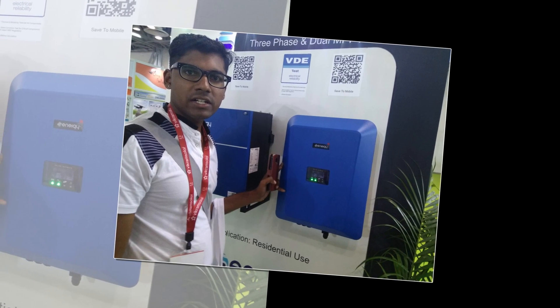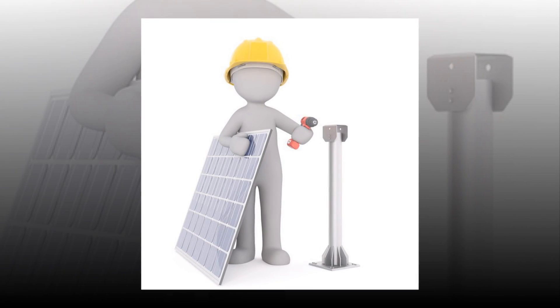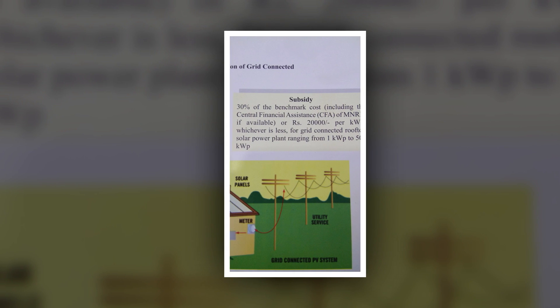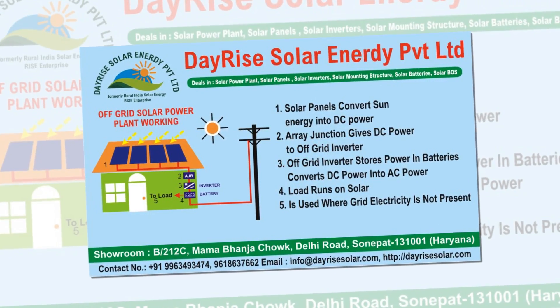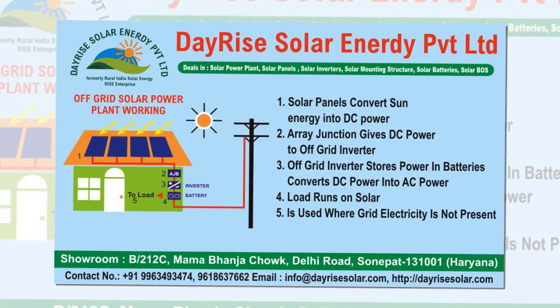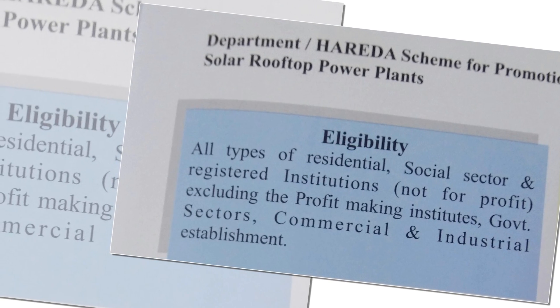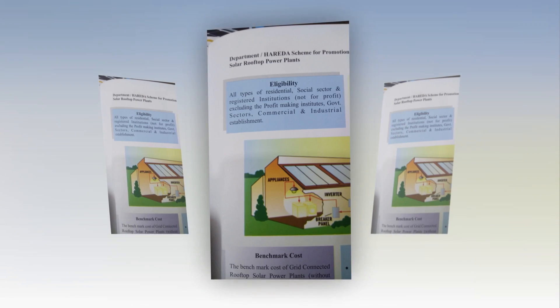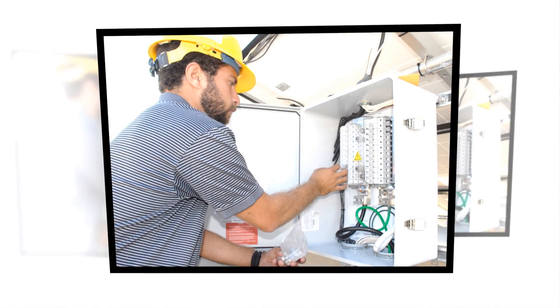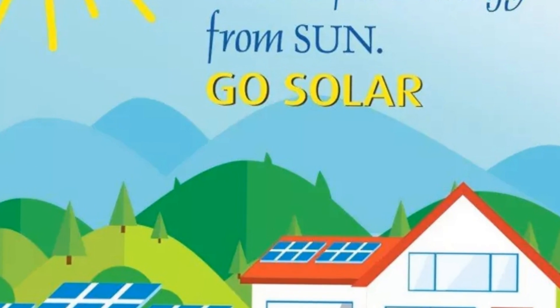What size of solar power plant for houses in Sonipat would be sufficient? Typically, an owner of a 2,000 to 2,500 square foot home may consider installation of a solar power plant consisting of solar arrays of 4 to 5,000 watts — that is, a 4 or 5 KWP solar power plant. Depending on the type of panel chosen, a system of this size would require anywhere from 16 to 20 solar panels of 250-watt modules at 24V. Simply divide total monthly unit consumption by 30 to estimate your one-day requirement. A 1 KWP solar power plant may produce 4 to 5 units per day under ideal sunlight conditions for 300 clear sunny days in Sonipat, India.